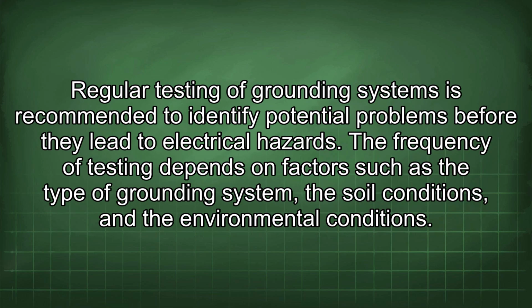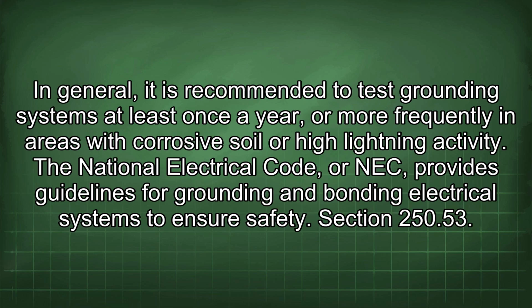Regular testing of grounding systems is recommended to identify potential problems before they lead to electrical hazards. The frequency of testing depends on factors such as the type of grounding system, the soil conditions, and the environmental conditions. In general, it is recommended to test grounding systems at least once a year, or more frequently in areas with corrosive soil or high lightning activity.